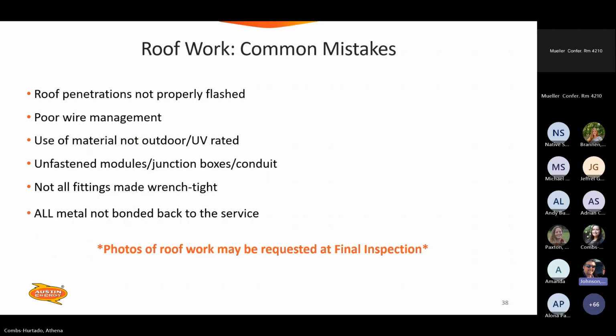Not all fittings made wrench tight. They need to have actual tools placed on the fittings. There should be teeth marks on fittings from channel locks actually making them wrench tight. We don't want this stuff coming undone from the vibration of voltage flowing through the system over time. All metal not bonded back to the service. So all the metal must be created as one bonded system in some form or fashion. If you're not using appropriate grounding lock rings, then a grounding bushing would be required to make sure everything is bonded back to the source. All right, next, please.